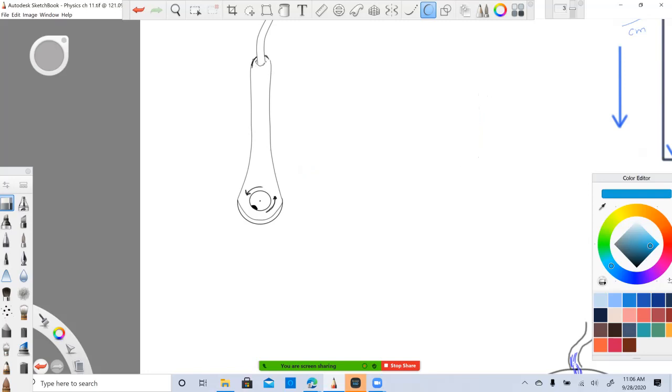But there's also a way of creating a more active picture. Most of those single element transducers that don't move or anything, they don't produce a picture. They're probably a continuous wave transducer. So no backing material on them. They just ring, ring, ring, ring, ring nonstop. And so they're used for vascular studies. But we can create a single element transducer that produces a picture. And it's done, well, mechanically.